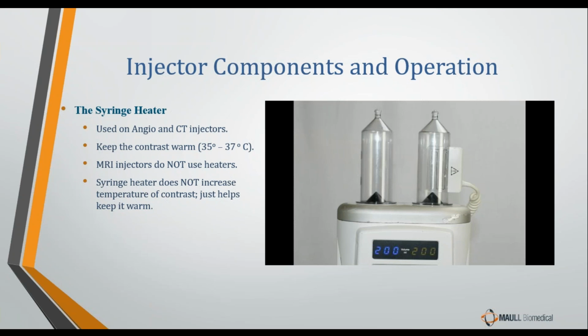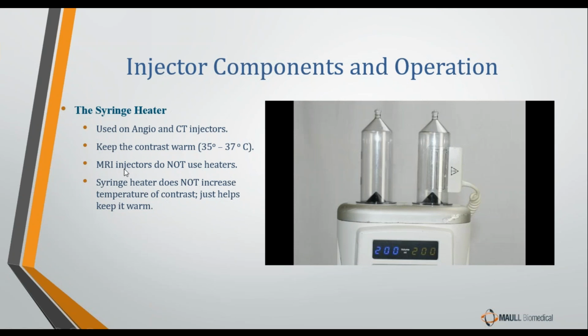Now, some syringes, and this is based on the type of contrast injector that we're using, actually have heaters connected to them. Now, angio injectors and CT injectors, because both of these systems use X-rays to produce the images, they are both using an iodine-based contrast fluid to produce the angiographic images. So because both angio and CT injectors use iodine, if you guys have ever worked with it, it's very thin. It's nearly as thin as water, but there is a slight syrupy texture to it. So to help keep our pressures from being built up too much in the syringe during an injection, we will warm the contrast up. Everybody knows when you warm syrup up, you lower its viscosity, it becomes more runny.